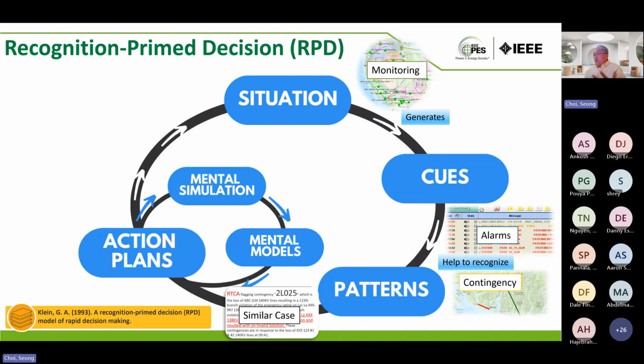Because it's a pretty simple unit trip, you look for a reserve plan and know what to do; it's a pretty simple actionable plan. Maybe automatic generation control, or AGC, already kicked in to arrest the frequency drop. However, if it's a new situation, with many alarms and other generators tripped, that may not be the right action plan, so you cannot just rely on AGC to help the situation.